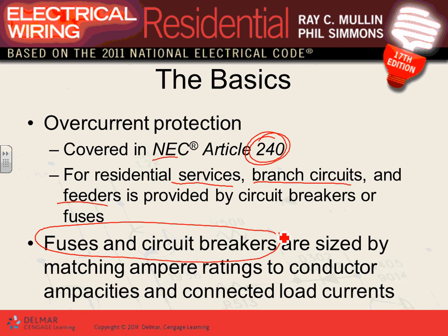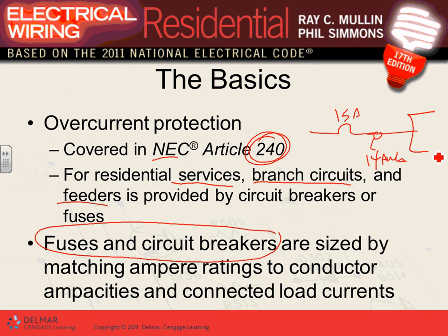When we size fuses and circuit breakers, we size them based on the ampacity of the conductors and equipment. For example, if I have a 15-amp circuit breaker, I know I can put number 14 AWG, and non-continuously I can pull 15 amps. Number 14 is capable of carrying up to 15 amps under normal operating conditions per the code.